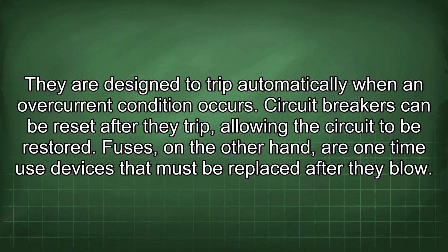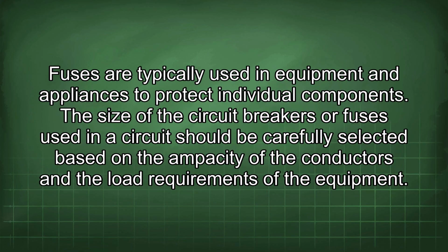Circuit breakers can be reset after they trip, allowing the circuit to be restored. Fuses, on the other hand, are one-time use devices that must be replaced after they blow. Fuses are typically used in equipment and appliances to protect individual components. The size of the circuit breakers or fuses used in a circuit should be carefully selected based on the ampacity of the conductors and the load requirements of the equipment.